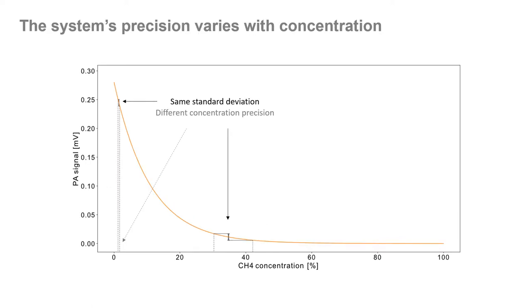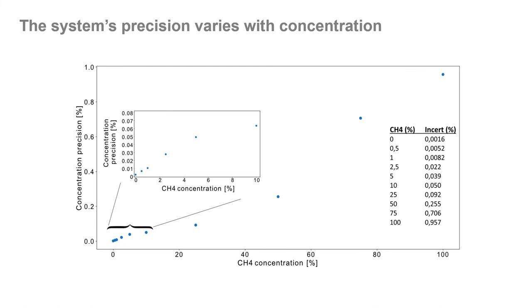Because of the curved shape of the fitting function, it means that the system's precision varies with concentration even for a photoacoustic signal with the same standard deviation. This means that the precision gets better at lower concentration and a bit worse at high concentration. However, this can be beneficial if we happen to be looking for small amounts of gases.